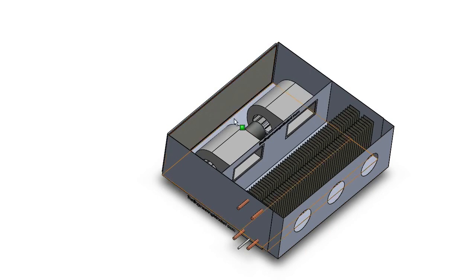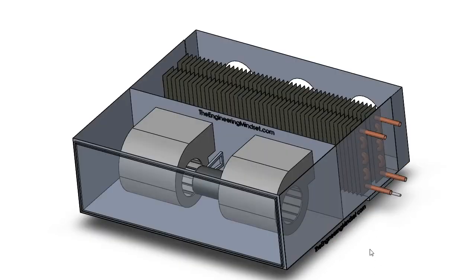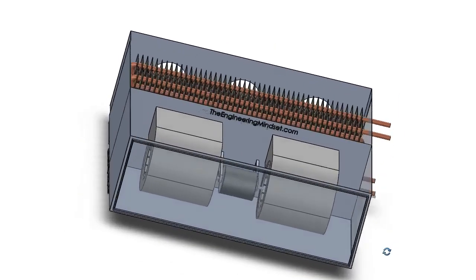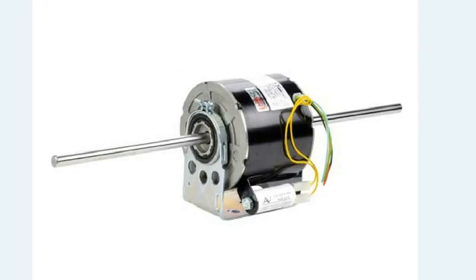Once the air is pulled through the filters it enters the fans. In a fan coil unit you can have one, two, or three fans — two fans is fairly common. Driving these is a small motor located in the middle, connected to the fan blades inside. These fans are usually quite small, around 80 watts, with a shaft through the middle onto which multiple fan blade cages can be connected.